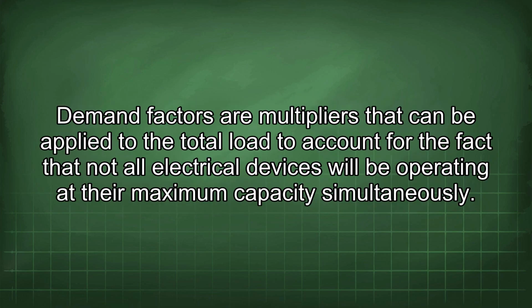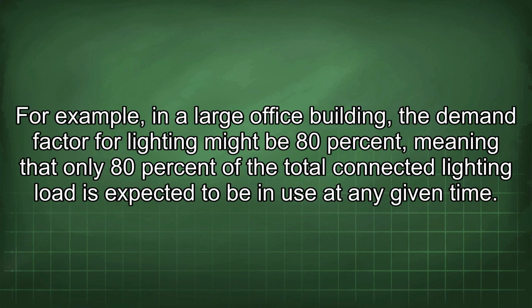Demand factors are multipliers that can be applied to the total load to account for the fact that not all electrical devices will be operating at their maximum capacity simultaneously. For example, in a large office building, the demand factor for lighting might be 80%, meaning that only 80% of the total connected lighting load is expected to be in use at any given time.